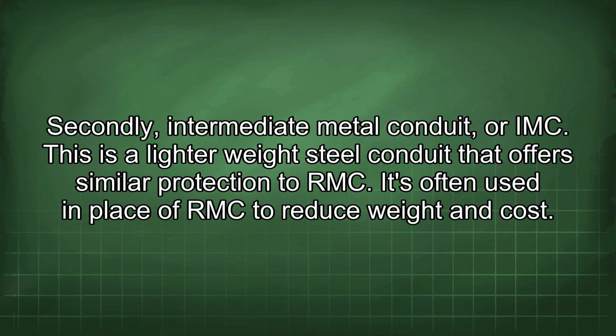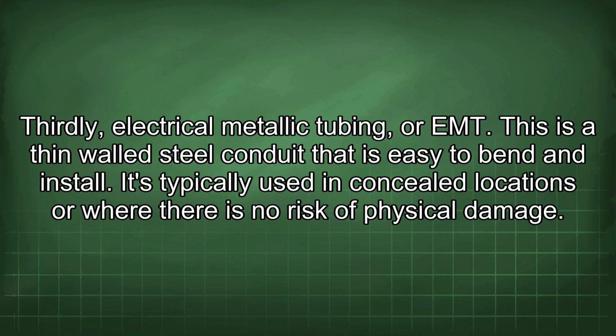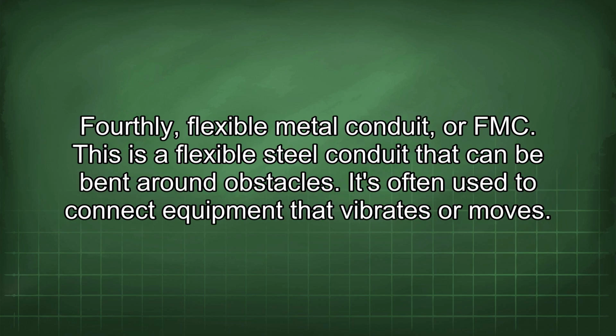Secondly, intermediate metal conduit or IMC. This is a lighter weight steel conduit that offers similar protection to RMC. It's often used in place of RMC to reduce weight and cost. Thirdly, electrical metallic tubing or EMT. This is a thin-walled steel conduit that is easy to bend and install. It's typically used in concealed locations or where there is no risk of physical damage. Fourthly, flexible metal conduit or FMC. This is a flexible steel conduit that can be bent around obstacles. It's often used to connect equipment that vibrates or moves.